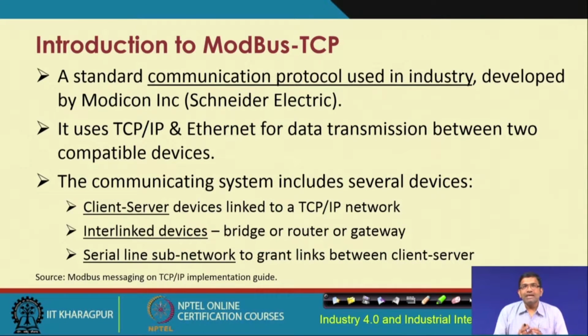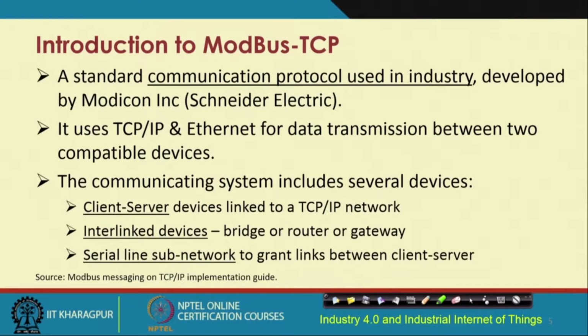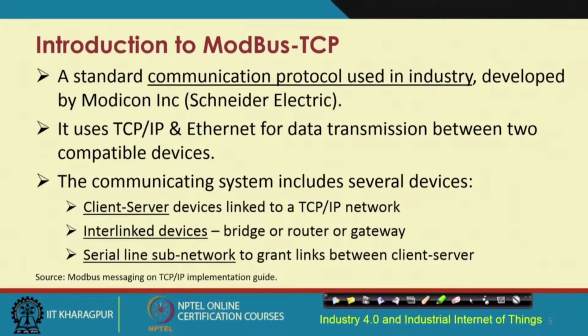Modbus TCP has different types of communication in the different devices that they have. First of all, they use the client server based mechanism for communication, which is quite well known. What is the client server mechanism? Client server communication is used, and for that the conventional TCP IP is used for the communication between the client and the server. The next one is devices such as bridges, routers, gateways, etc., which interlink different parts of the network, right. So, that is the interlinking devices part, and the third one is the serial line subnetwork that basically provides the links between the client and the server. So, these are the three parts of the communication system used in the Modbus TCP protocol.